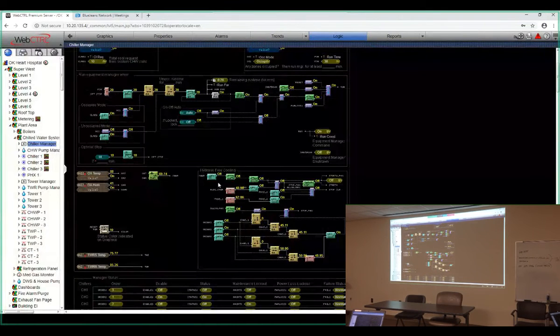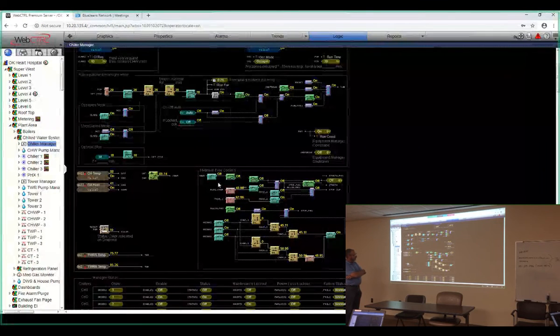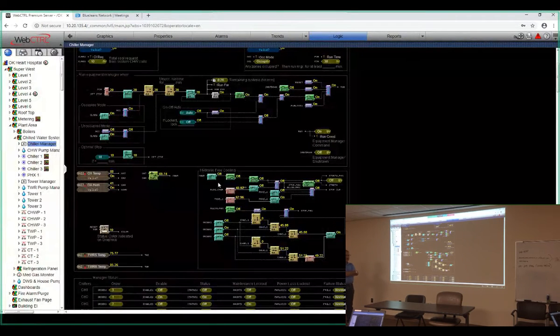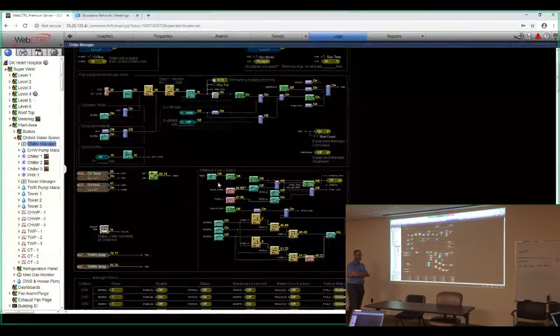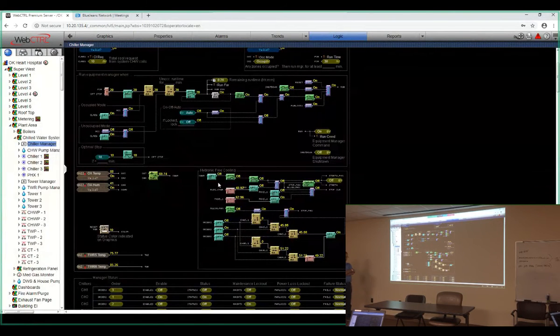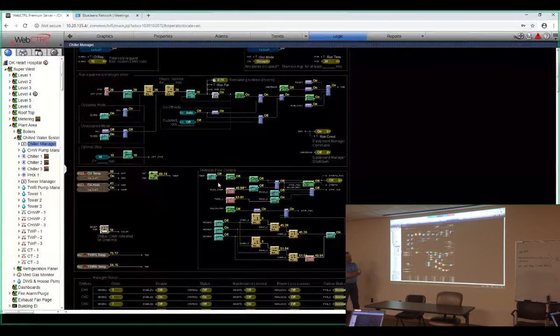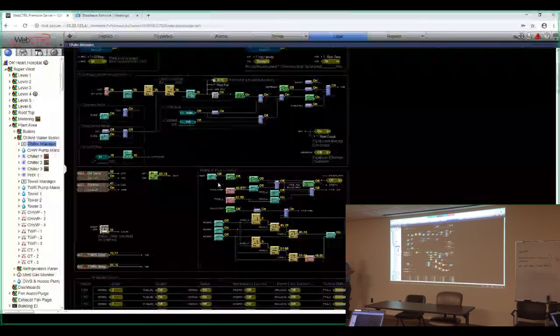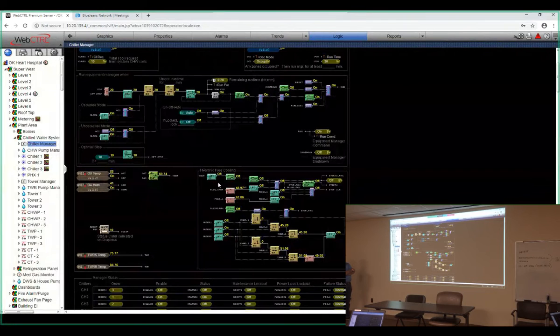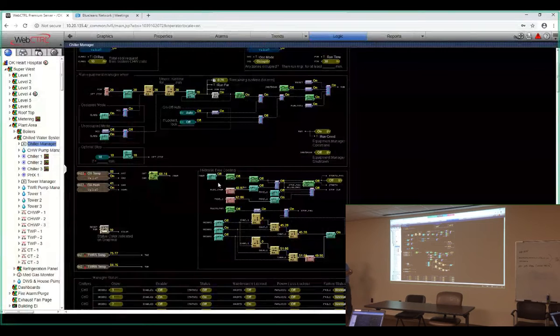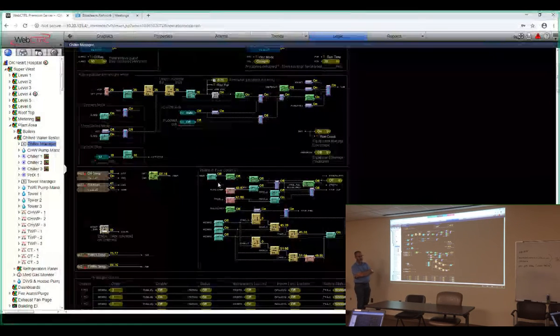It will run in that mode until our heat exchanger supplied temperature gets above 62, and then it'll come out of that mode. Bring the chiller back on, reset the temperatures back to 75 on the cooling towers, and then start the chiller. So we go into that mode at 33. We take the condensing water temperature down to 49. Once we get below that set point, I'm going to stop the chiller, open the valves on the heat exchanger, and run in that mode until we get above 62 on our chill water temperature.